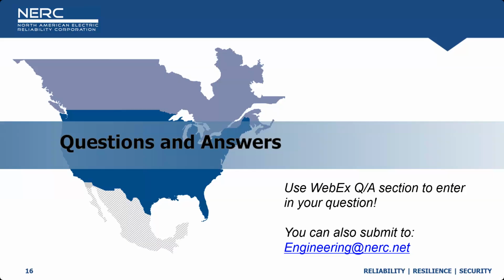However, that's also potentially something that can be installed after the fact of interconnection, though it may follow a different process than the interconnection processes and procedures. You may have to work with that individual customer to install potentially utility-owned equipment in order to monitor the fault and disturbance-based recording of that facility. So what recommended equipment? I would start with fault recordings, and then keep broadening out into other communications architectures so operators can monitor and understand the impacts that facility has on the bulk power system. Evan, do you want to add a little bit?